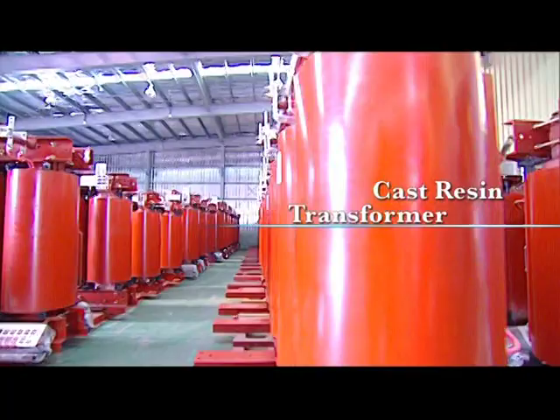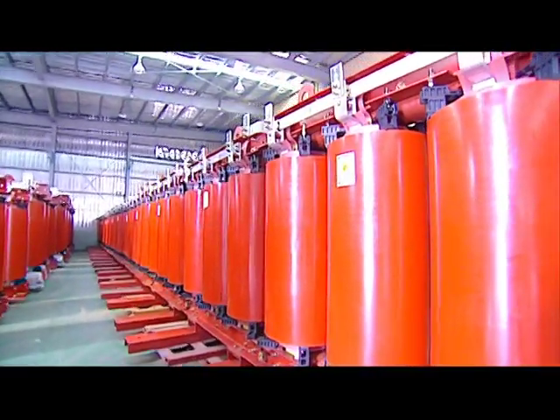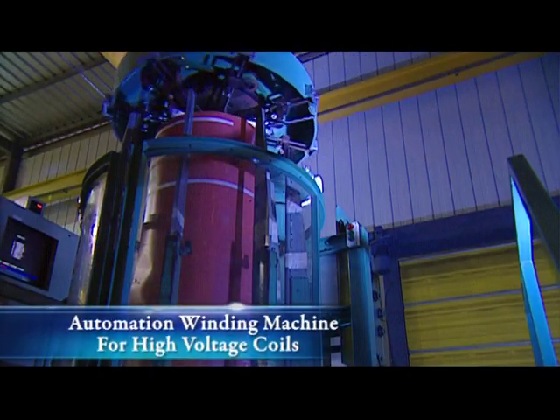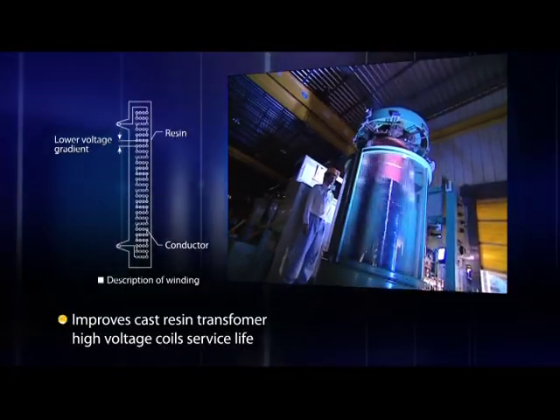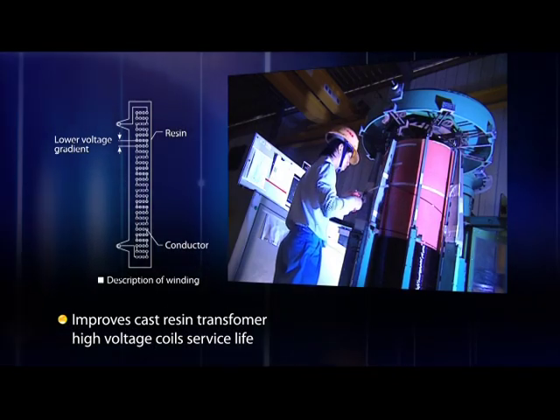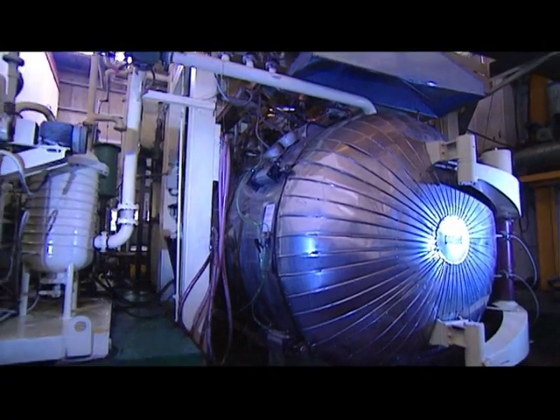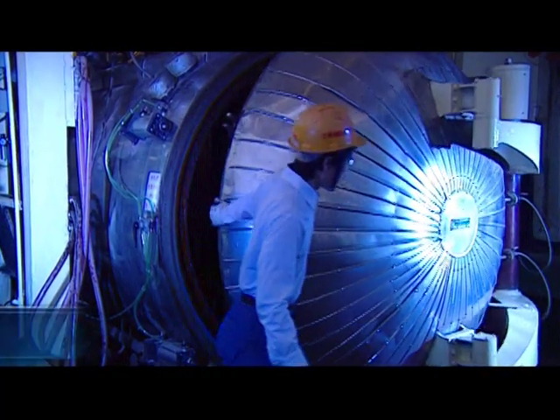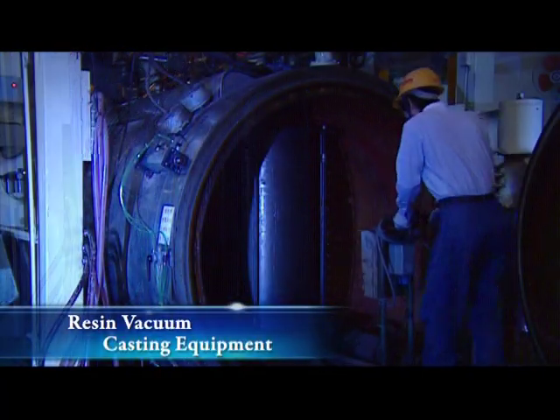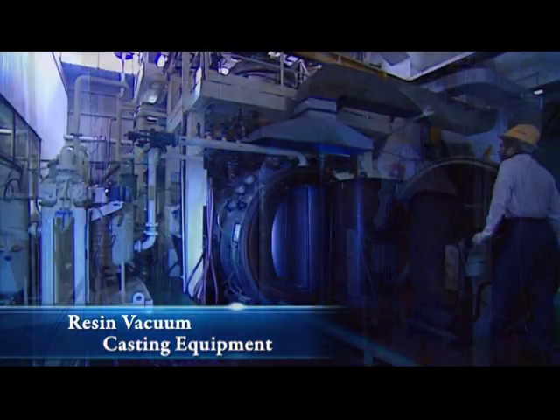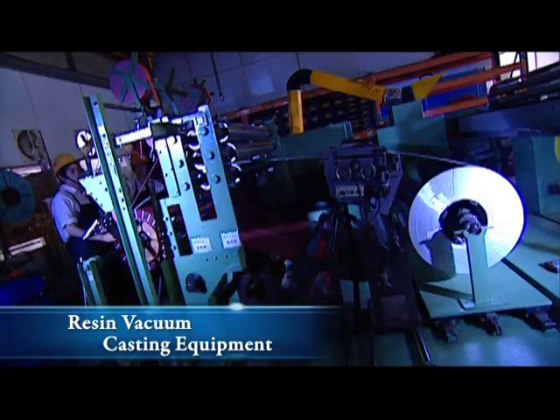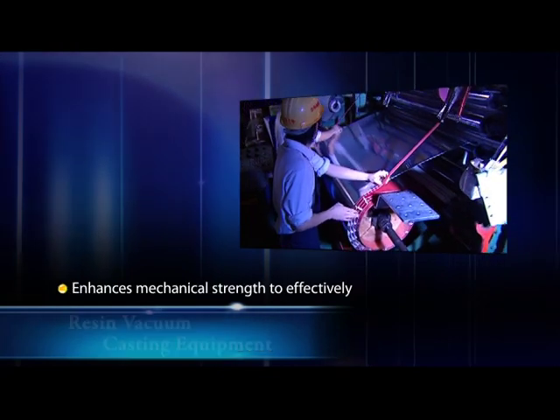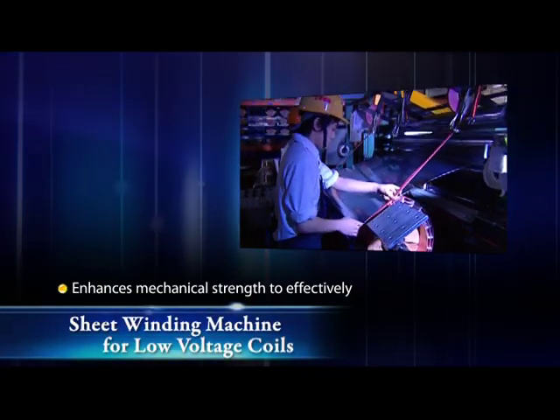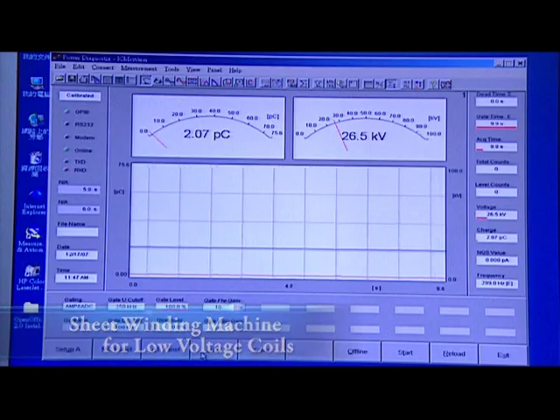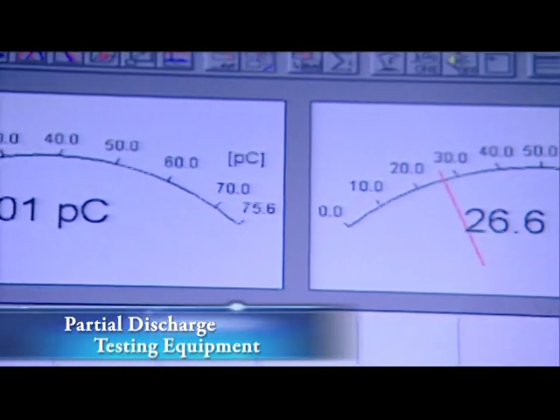SHIHLIN Electric's cast resin transformer is built using computerized automatic vertical coil winding equipment. Its unique winding technology allows uniform and well-distributed electropotential in primary coils that further reduces partial discharge from minimum potential differences. The cast resin transformer plant applies an Italian-made automatic epoxy resin filling system to ensure primary coil vacuum epoxy resin filling quality. The technology and process deliver a partial discharge performance that is well below industrial standard 10 pC.